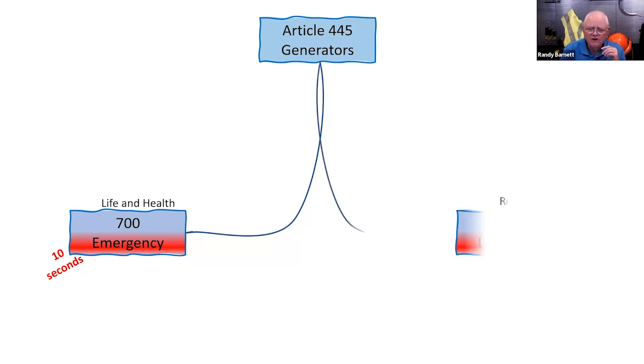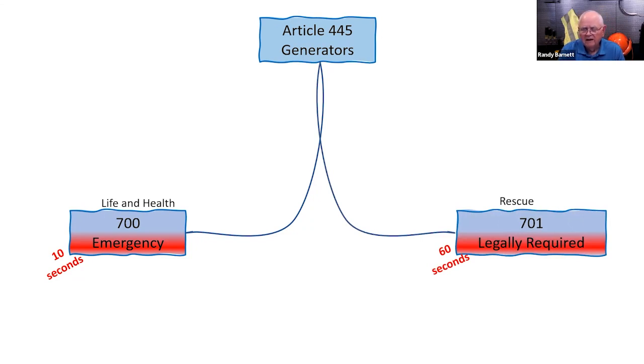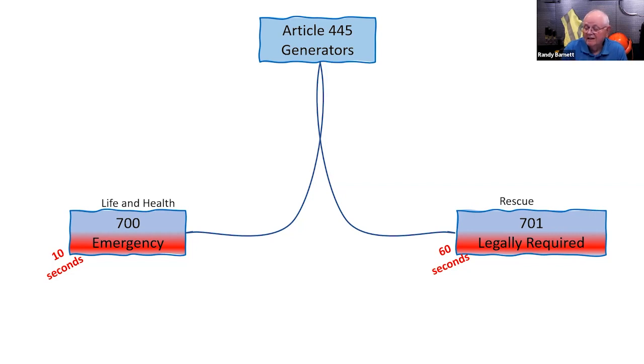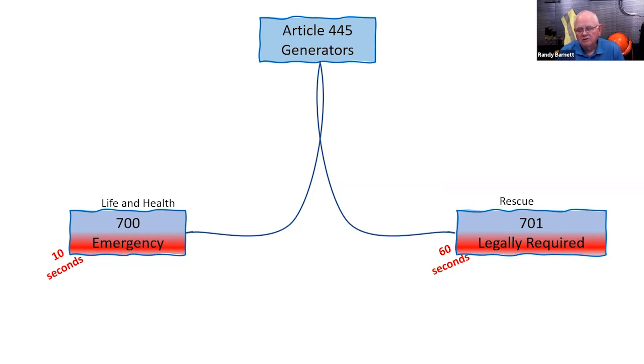We also have Article 701, for legally required standby systems. The terminology says they're less critical — not as important to human life and health. The code even uses the term 'rescue operations.' In Article 700, if the power goes off and we don't get emergency power back within 10 seconds, we have a danger of losing someone's life — or damage to health due to bad vapors, fumes, improper ventilation, smoke.